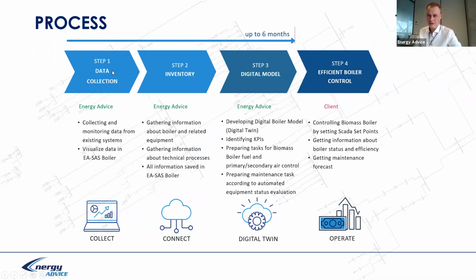In the timeline, we collect the data. If you have already collected data to the cloud, and this data is, for example, in the second-minute range, depending on parameters, sometimes we need minute range data, sometimes we need second range data. We collect data to our cloud. We do an inventory of your boiler system. I mean all parameters, including fans, air supply, flue gas, oxygen meter, furnace, heat exchanger, etc. All components which describe a boiler. We make the digital model, the digital twin, and you have operation.